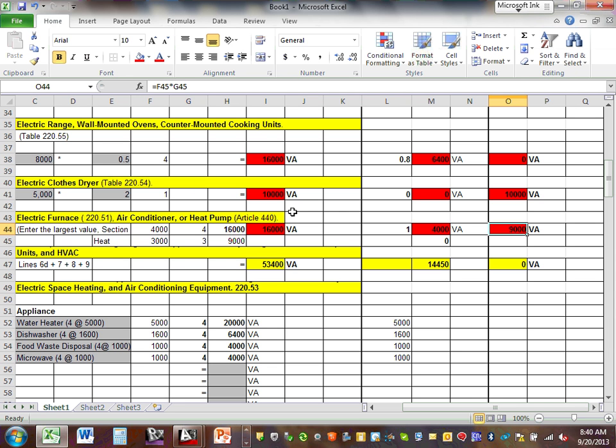Before I leave this step, Karen, any question why this is a 4,000 here and why this is 9,000? Because the common panel is going to have 3 heaters. Each heater is going to be 3,000. The 3 of them will be 9,000. Are there any air conditioning to compare with under the common panel? No. So you leave them alone. Same thing. Come to the apartment panel.